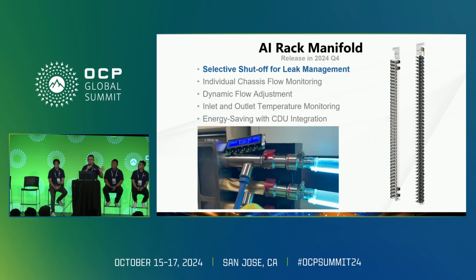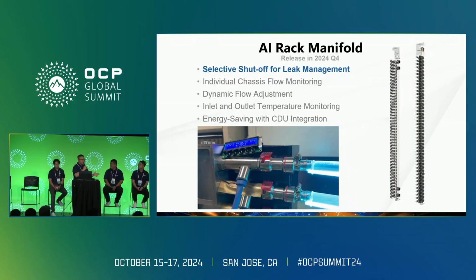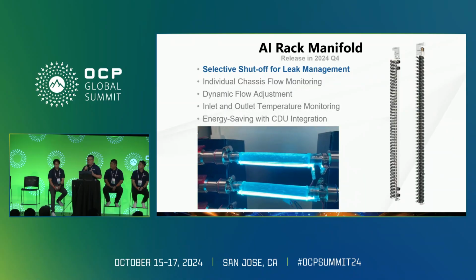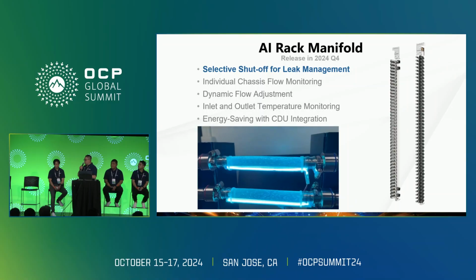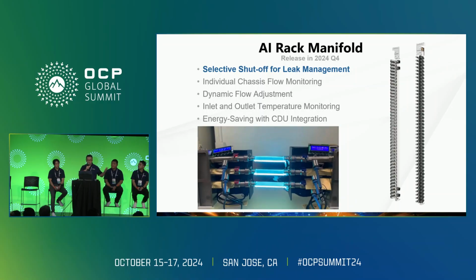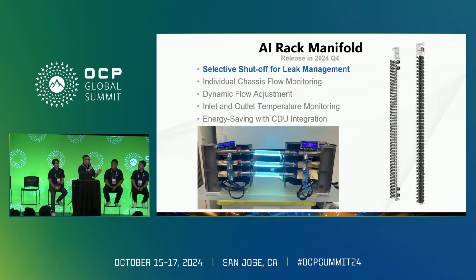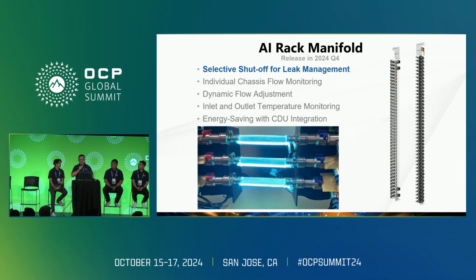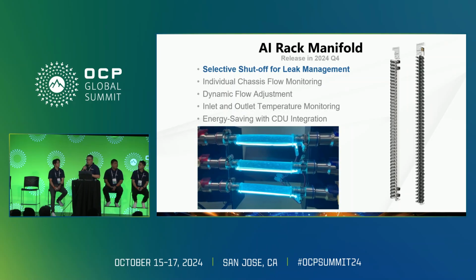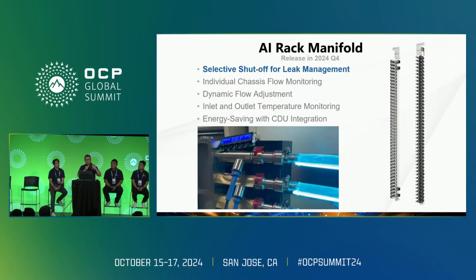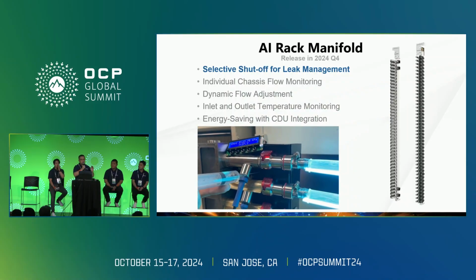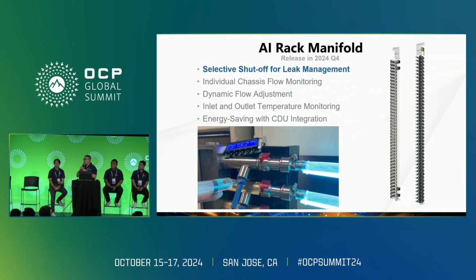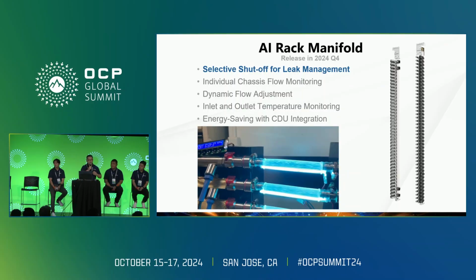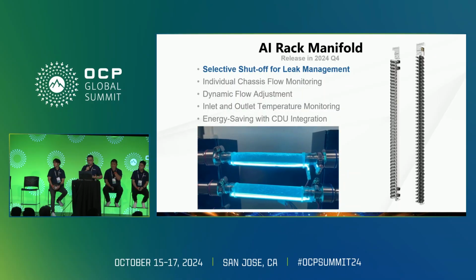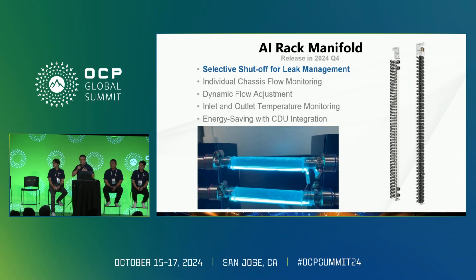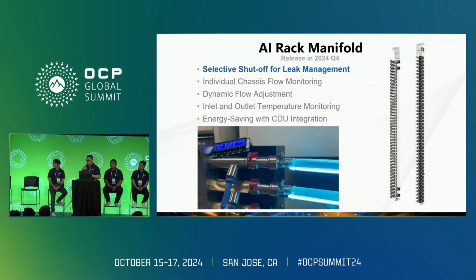Compared with conventional models, our AI manifold offers, number one, protection. When there is any leakage detected in a certain rack, with our new rack manifold, when the problem rack is shutting down, the liquid supply of that rack can be cut off at the same time to prevent the condition from becoming worse, while the unaffected racks can still work properly.